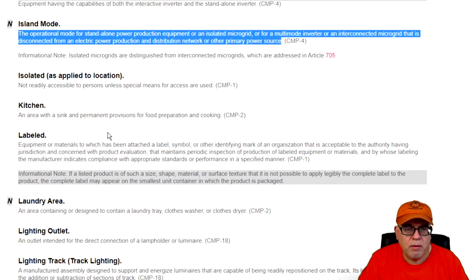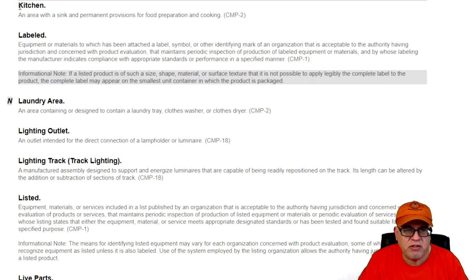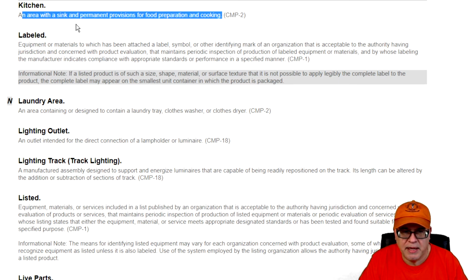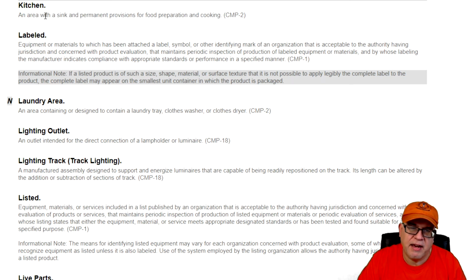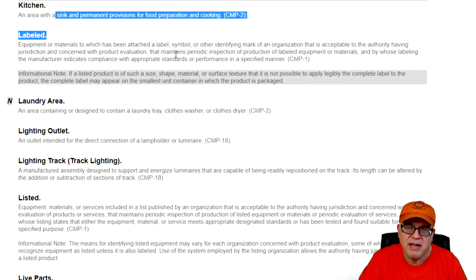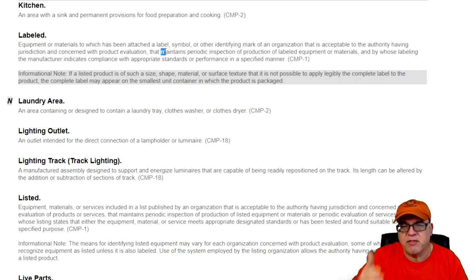All right, next one that's important, obviously, for us. We know what a kitchen is, but it is real important that we understand that a kitchen is an area with a sink and permanent provisions for food preparation and cooking, okay? So it has all these elements. Note it doesn't say an area with a sink or permanent provisions for, it has ands in there. And the ands are chained, which means it's this and that, not this or that. So to be a kitchen, it has to have the sink, it has to have permanent provisions for food preparation and cooking to qualify as a kitchen.